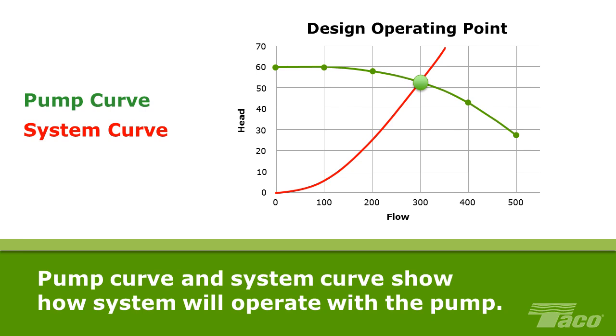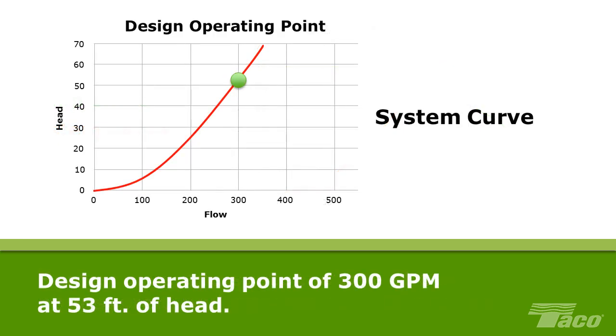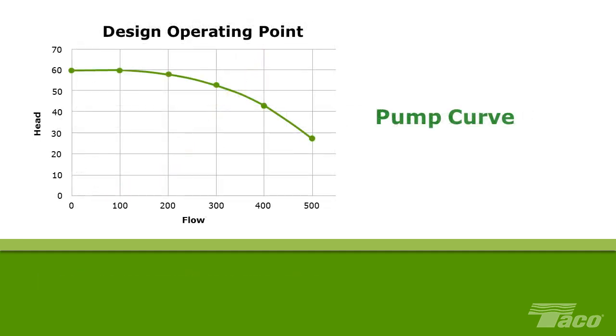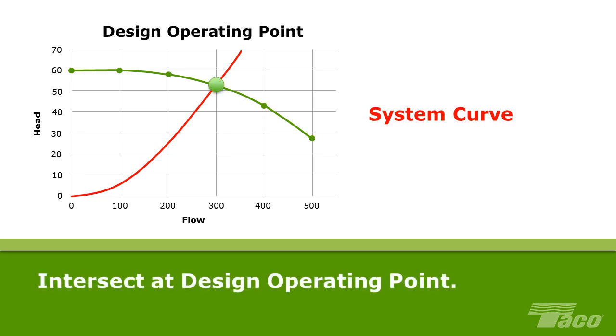However, the point at which they intersect at any given time provides the hydronic engineer with essential information about how that particular system will operate with this pump installed. Here's the system curve we plotted earlier for our sample system with a design operating point of 300 GPM at 53 feet of head. Here's the pump curve plotted for the KS4009 shown earlier. This pump and any constant speed pump can only operate on its performance curve. When we overlay the pump curve on the system curve, they intersect at the design operating point.